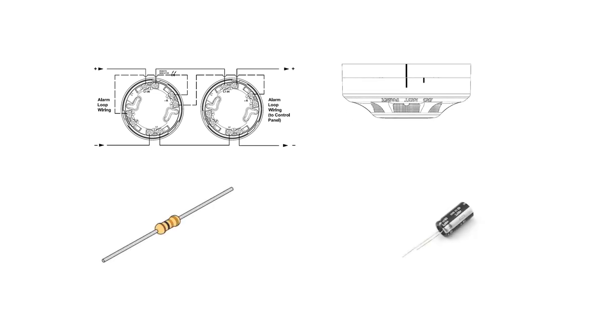Ensure all field connections are securely made and devices are connected to their bases. Check that all end-of-line devices are fitted, either to the last device on the detection zone circuit, the last device on the alarm zone circuit, or to the output terminals on the control panel where the zone circuit is not used. Finally, check that the earth connections are secure.